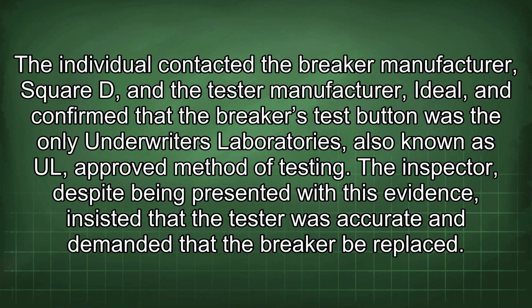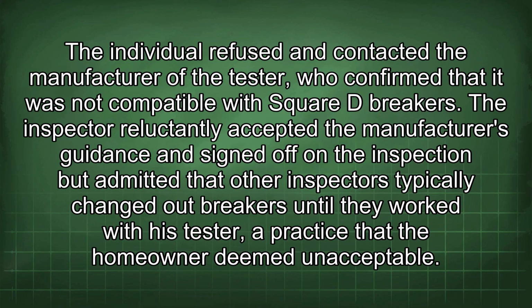The individual contacted the breaker manufacturer, Square D, and the tester manufacturer, Ideal, and confirmed that the breaker's test button was the only Underwriters Laboratories, also known as UL, approved method of testing. The inspector, despite being presented with this evidence, insisted that the tester was accurate and demanded that the breaker be replaced. The individual refused and contacted the manufacturer of the tester, who confirmed that it was not compatible with Square D breakers.